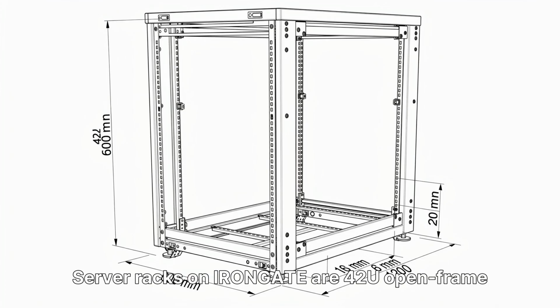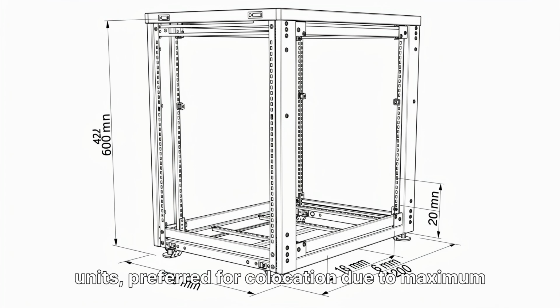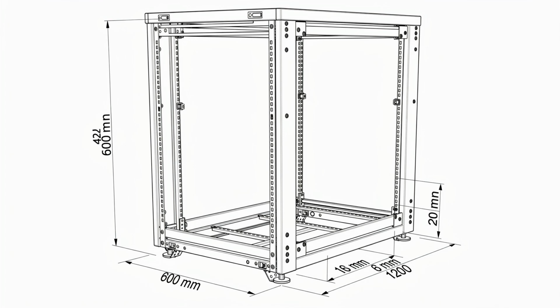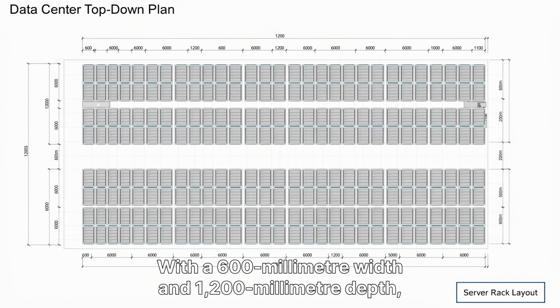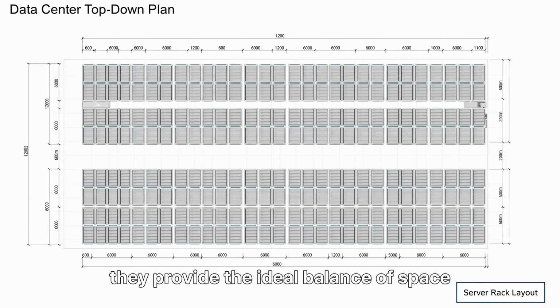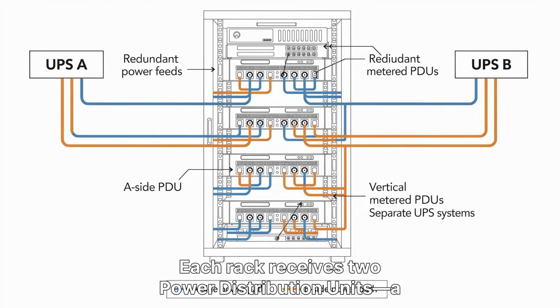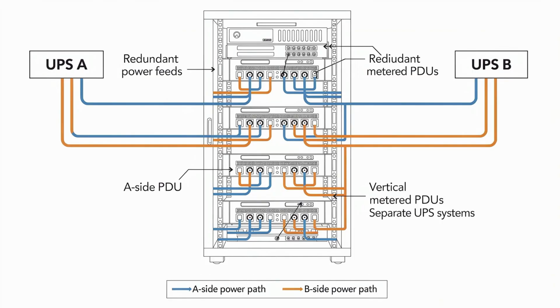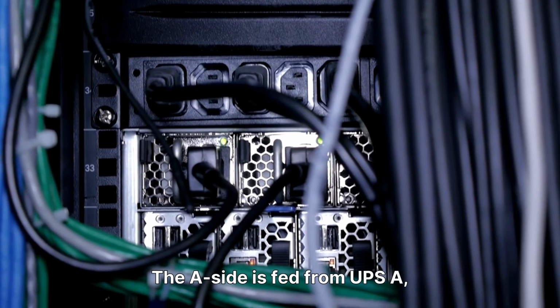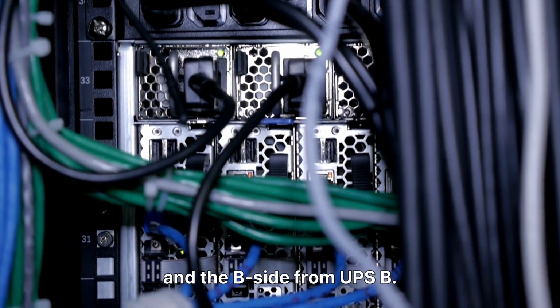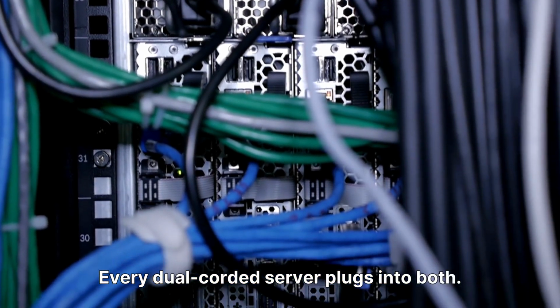Server racks on IRONGATE are 42U open frame units, preferred for co-location due to maximum airflow flexibility. With a 600mm width and 1200mm depth, they provide the ideal balance of space and management. Each rack receives 2 power distribution units, a PDU on the A side and a PDU on the B side. The A side is fed from UPS-A and the B side from UPS-B. Every dual-corded server plugs into both.